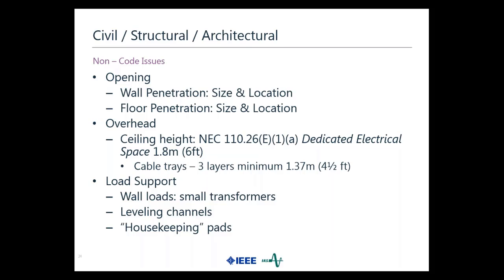I mentioned the project that we did out in California. One thing that we ran into was we had prefabricated buildings that we used out there, kind of stick built, but they were prefabricated, bring them on site, put them together. And we ran into a little surprise. The wall load on those was not capable of supporting very much. So a 75 kVA wall mount transformer for a lighting transformer, we actually had to build a little platform or support structure for that transformer, because we could not just hang it on the wall, if you will.